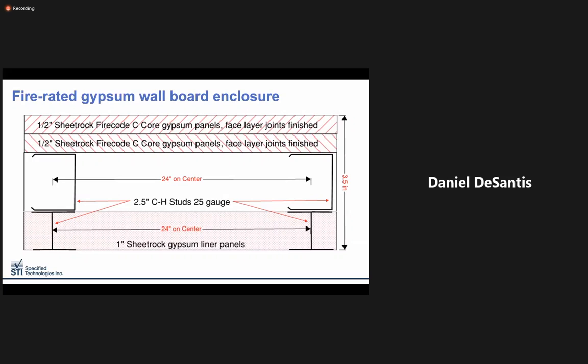Drywall enclosures for fire rating of electrical circuitry is the next and most common type of thermally protective system that we'll talk about. In this plan view of what a typical gypsum shaft wall construction looks like, the configuration on one side is 2 layers of 1/2-inch or 5/8 inch sheetrock, a 2.5-inch CH stud spaced 24 inches on center, and a 1-inch core board shaft liner on the reverse. This type of construction is commonly found in MEP riser shafts, elevator shafts, stair towers, and so forth. It's a great option for enclosing large shafts or creating area separation walls in both vertical and horizontal assemblies.